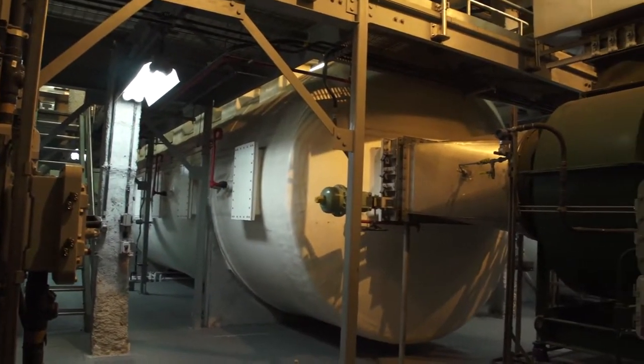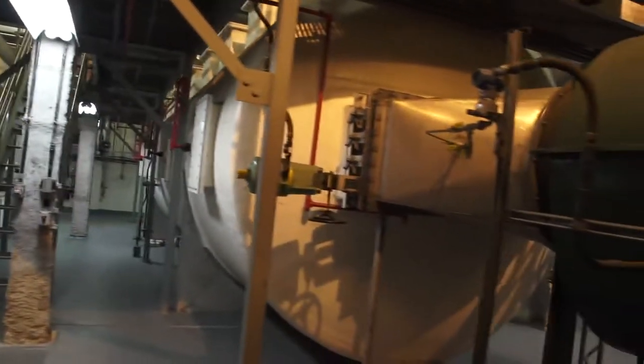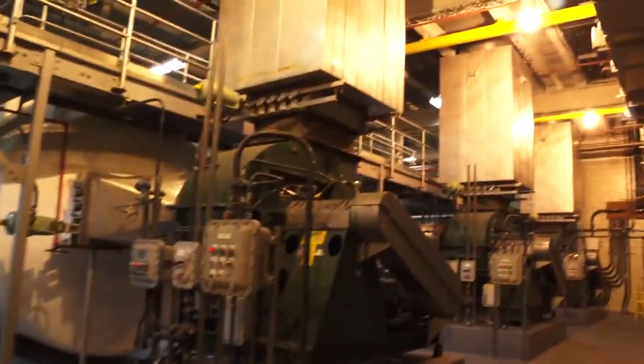It's really about why the screens are so important, and about odor and sound and noise, right? And this is the odor control. What you're looking at on the left here are the five carbon scrubbers that clean the air before it gets discharged out the roof. It's filled with activated carbon, so there are no chemicals, nothing like that. I'm able to run three of them and maintain the air in here. So as you can see, as you've walked around, you don't smell anything. Carbon's in there, yeah.